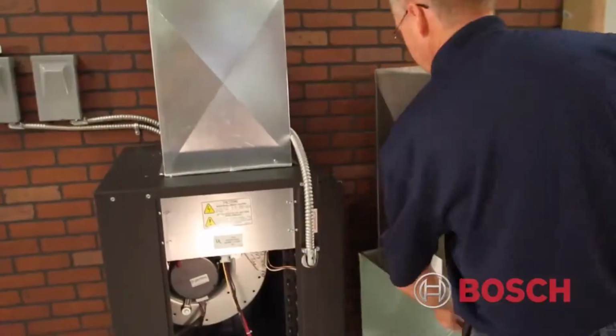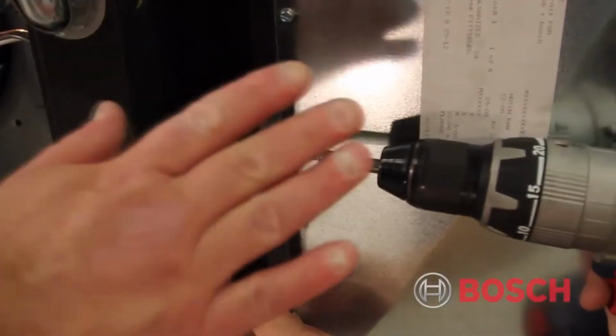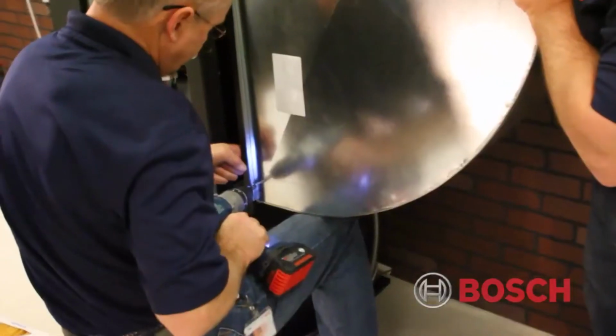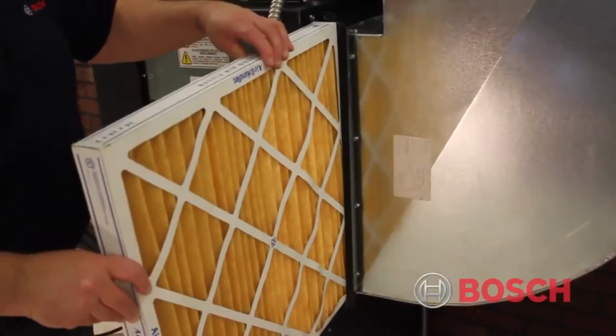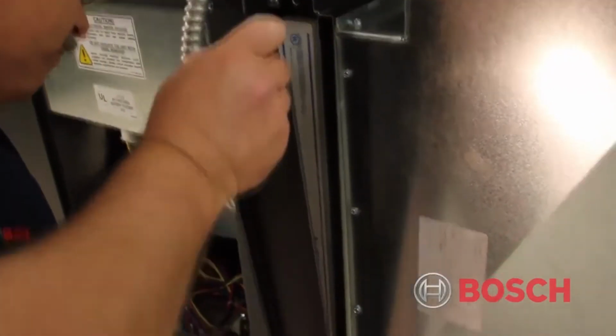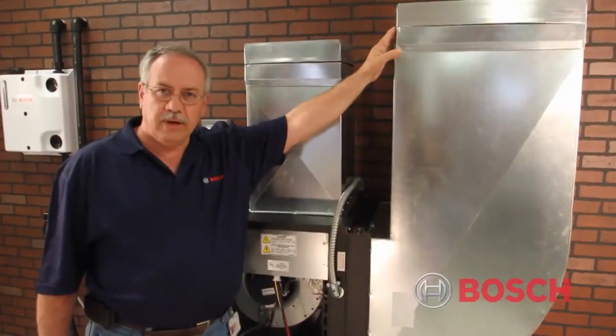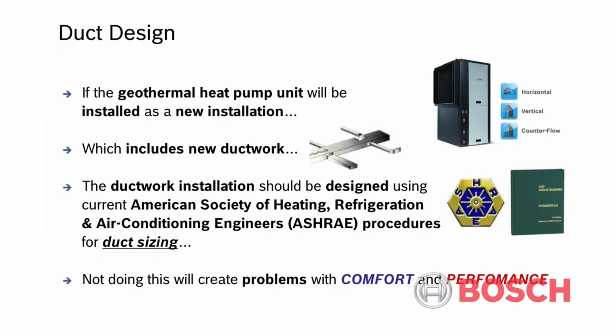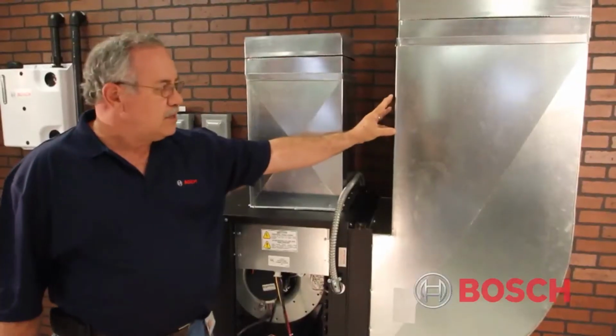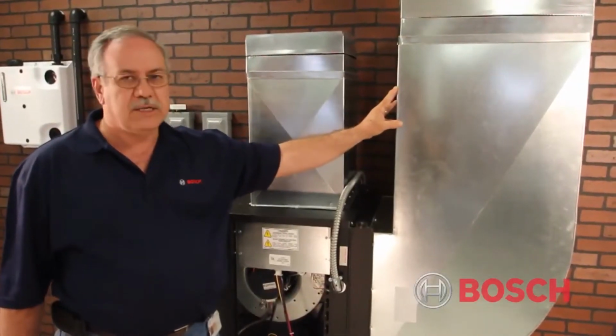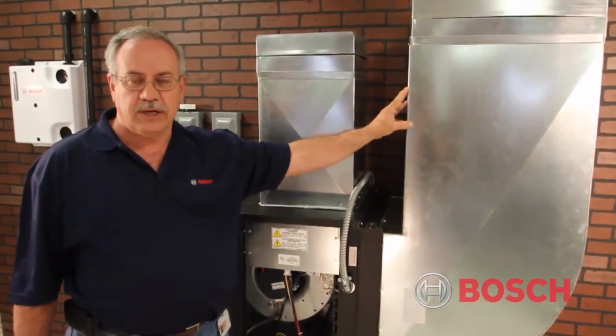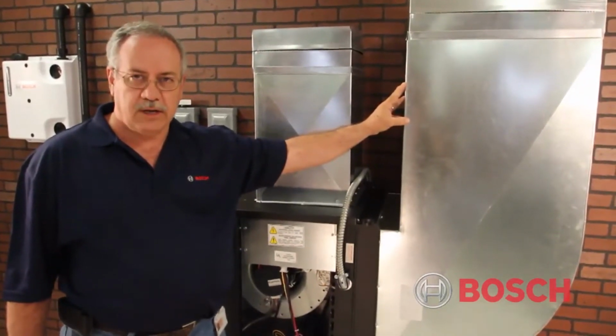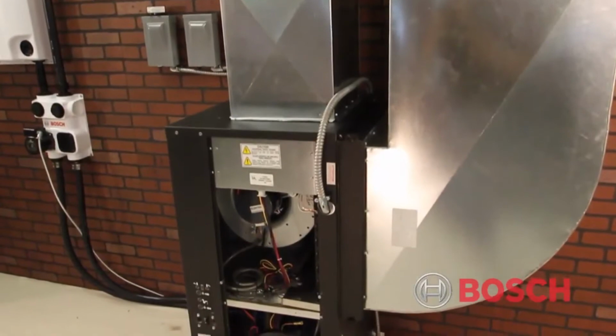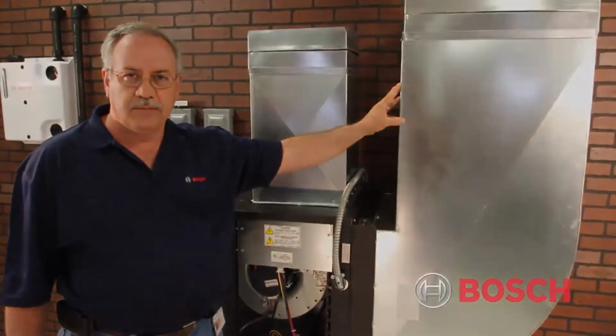Notice now that we have installed the return air plenum. We also have installed a flexible connector, assuming we're connected to metal ductwork also. When sizing either the supply or return ductwork, current ASHRAE standards and criteria must be followed. It is always recommended with metal ductwork that we insulate with at least 1 inch insulation, either internally or externally, to prohibit any type of condensation, especially during the cooling cycle.